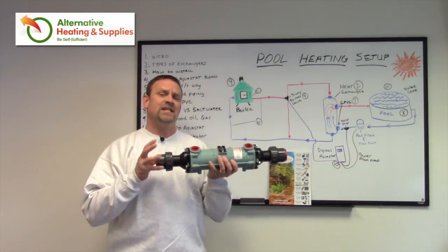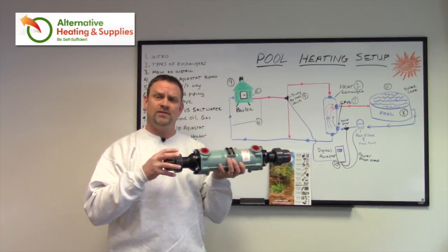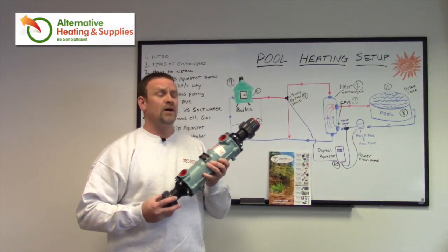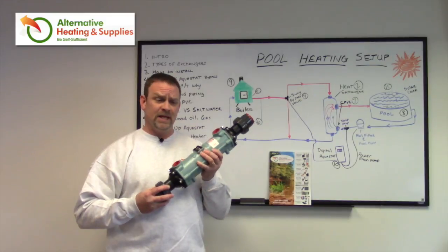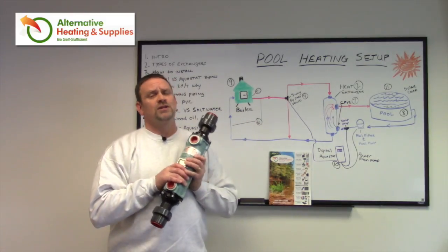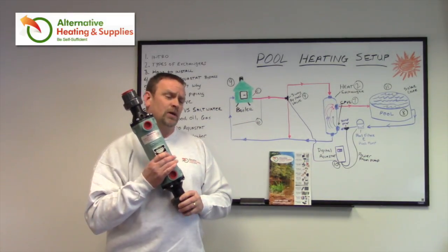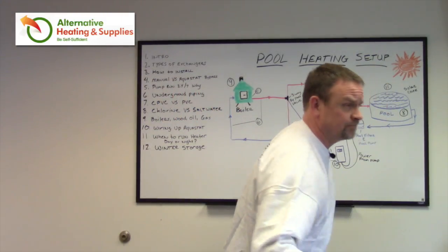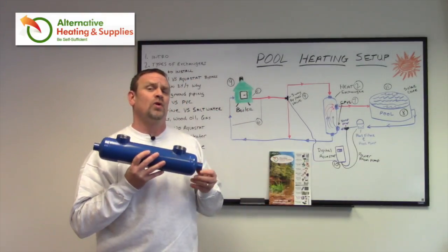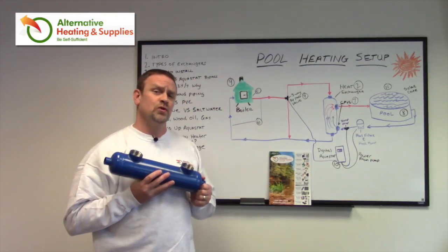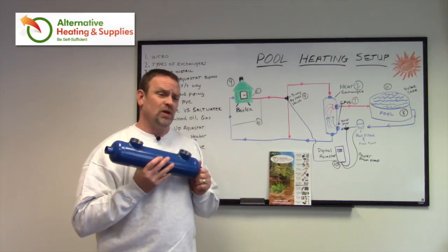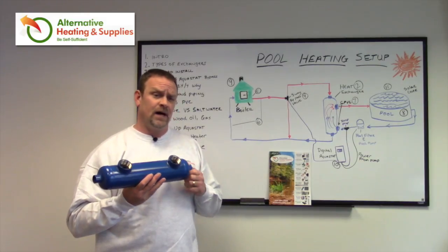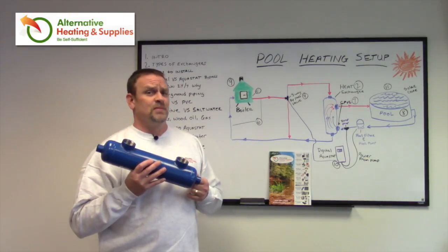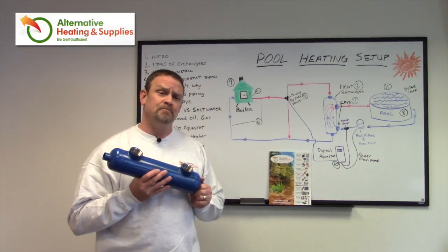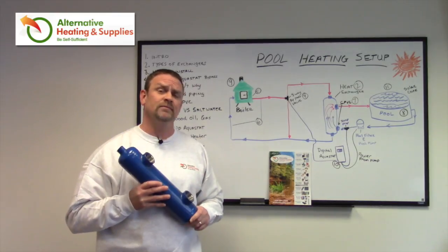They also come with a CPVC union to take on and off as your season comes to an end and at the beginning. And these are considerably more expensive because they can handle the salt water. The stainless steel cannot handle salt water for very long. It can do okay, but in a saltwater pool application, we recommend you go to the copper nickel. Saltwater heat exchangers will have a shortened lifespan, probably a lot longer than most people think, but we recommend that you go right to the copper nickel.